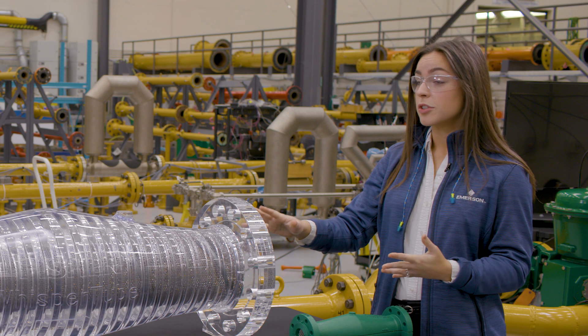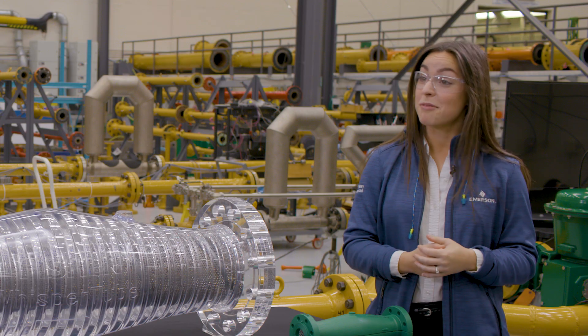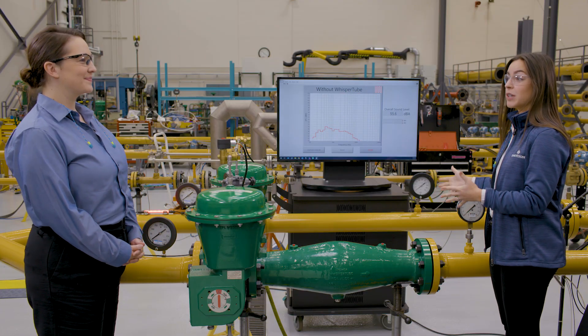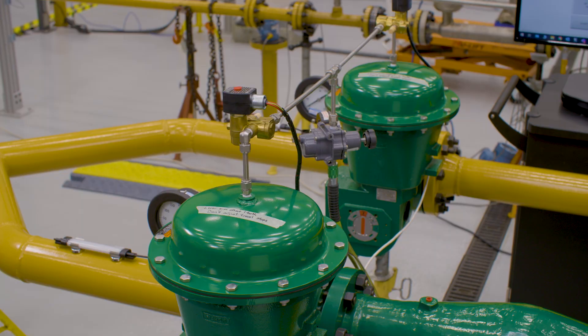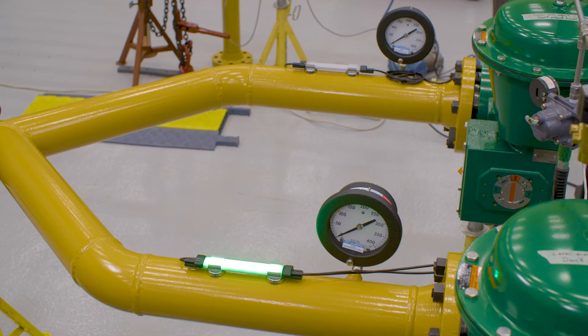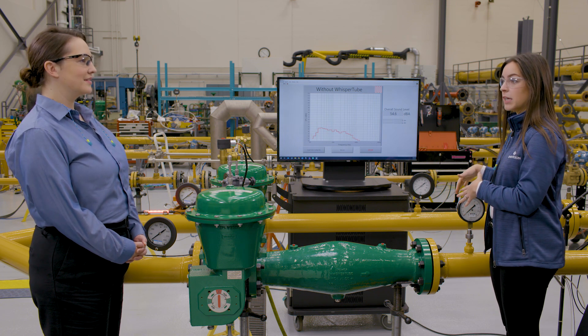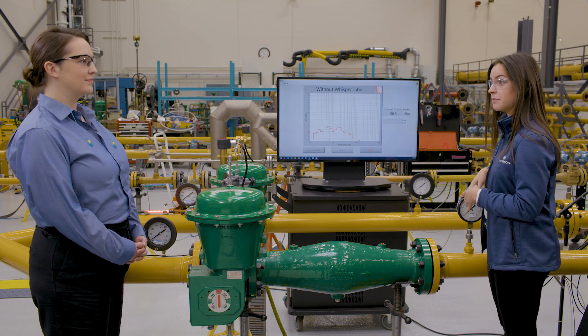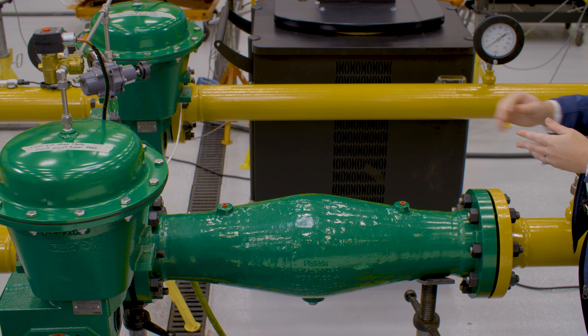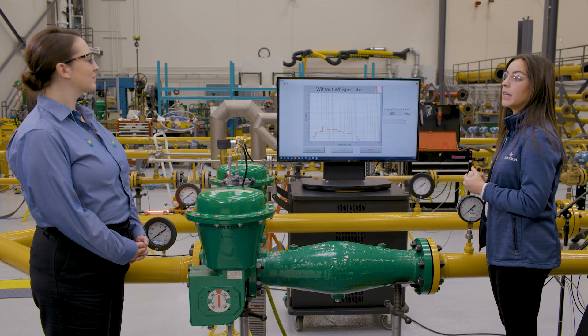How do you install the Whisper Tube? The Whisper Tube simply takes the place of a piece of pipe, and we have one installed right here. This demonstration is set up to show the noise difference between straight pipe and the Whisper Tube. It has two 4-inch Fisher V300s with travel stops at 0 degrees and 40 degrees rotation, which control which pipe has air flowing through it — lights show which valve is open and which is closed. When open, they will each flow about 90 CV with an 80 PSI pressure drop, visible on the gauges. One line has nothing installed in it, while the other has the Whisper Tube. Further downstream, two microphones take a reading of each line, and the readout is displayed on the screen.